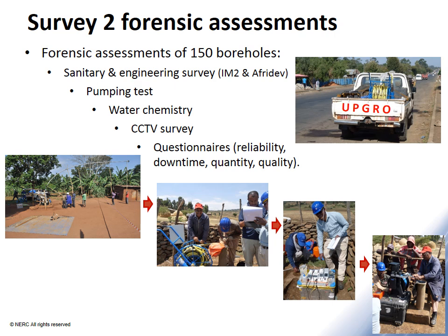To answer this question, we conducted detailed forensic assessments on 150 hand pump boreholes, which were a subsample of 600 hand pump boreholes used in Survey 1. We systematically dismantled the hand pumps — India Mark II and Afridev hand pumps. We conducted pumping tests to measure aquifer yield, took samples for water chemistry, conducted borehole CCTV surveys to assess construction, and asked communities questions about performance and reliability.